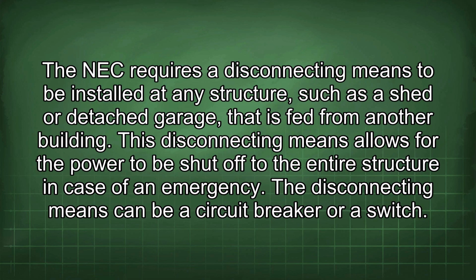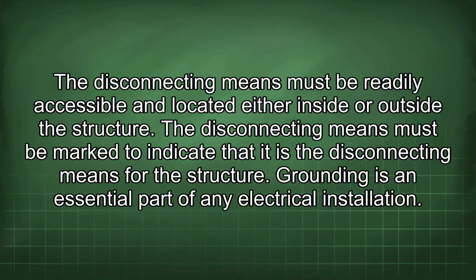This disconnecting means allows for the power to be shut off to the entire structure in case of an emergency. The disconnecting means can be a circuit breaker or a switch. The disconnecting means must be readily accessible and located either inside or outside the structure. The disconnecting means must be marked to indicate that it is the disconnecting means for the structure.